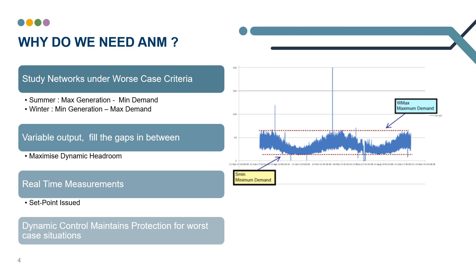This study method effectively caps the maximum amount of capacity we can connect. However, it does leave opportunity for variable output systems that effectively fill the gaps in between. By deploying real time ANM systems, we can make the most of this dynamic headroom available on the network and connect additional resource that may otherwise have required reinforcements.